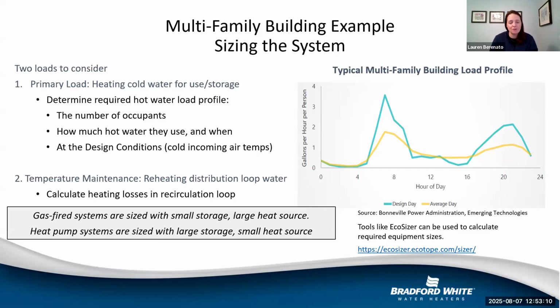This is just showing you the load profile for design day versus average day. I know most engineers design for worst case scenario, especially with their groundwater temperature. You typically will size for your winter months, not your summer months. So basically here you'll see gas-fired systems are sized with a small storage, large heat source. Exact opposite: heat pump systems are large storage and small heat source.